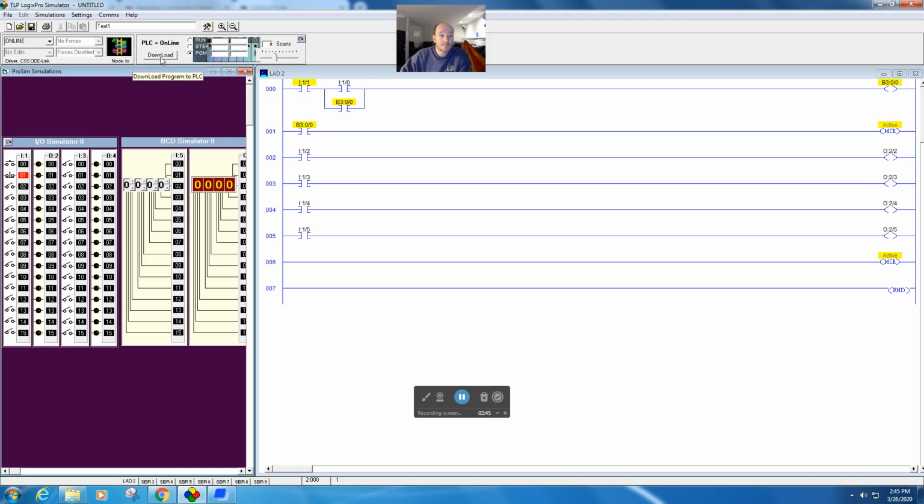So now let me make a small modification to show you the idea of the MCR. All I've done is moved my MCR up, and I've taken input 4 that's tied to output 4, and 5 that's tied to 5, and I've taken them outside of my MCR zone. Okay, so I'm going to download this and put it into run mode. Let's see what happens when these are outside of the MCR zone.